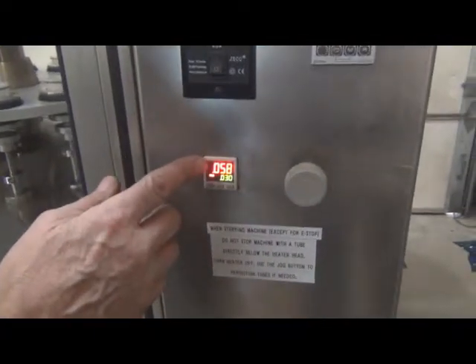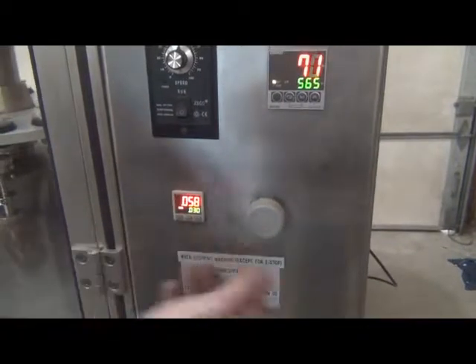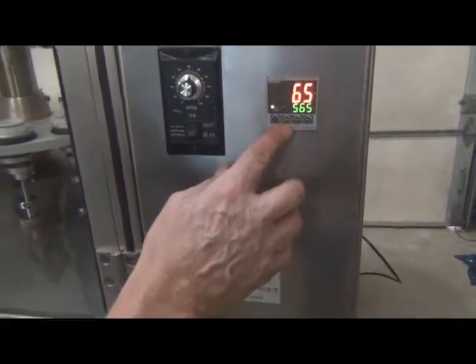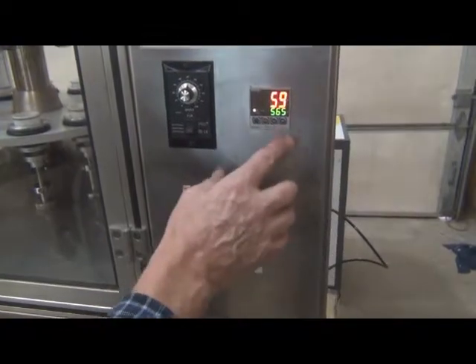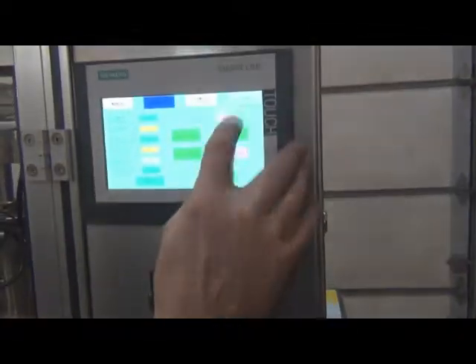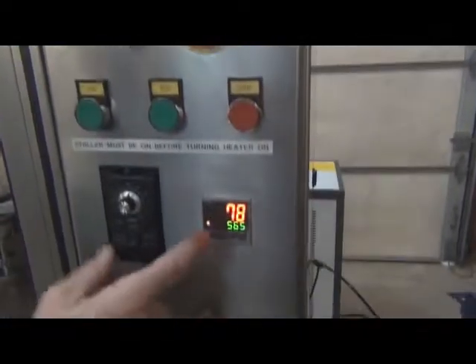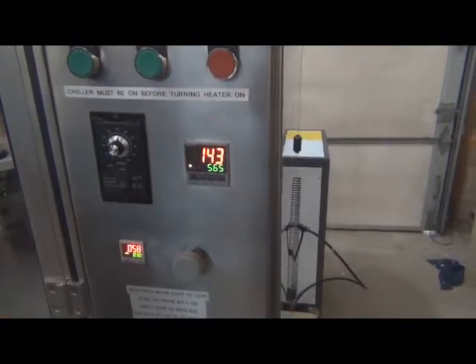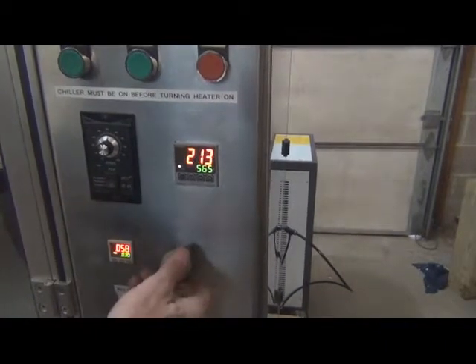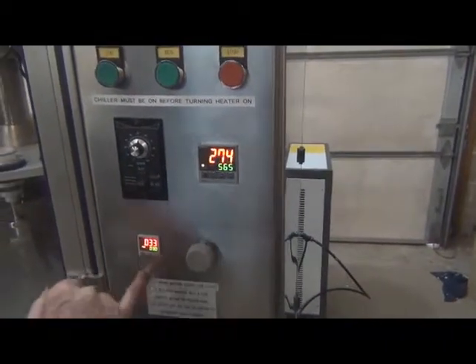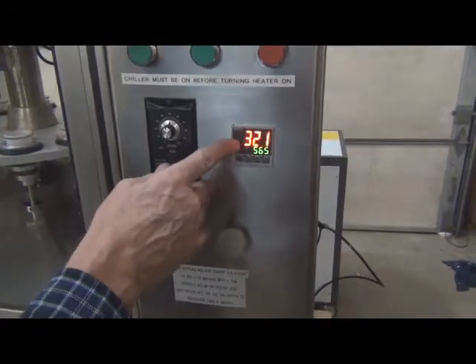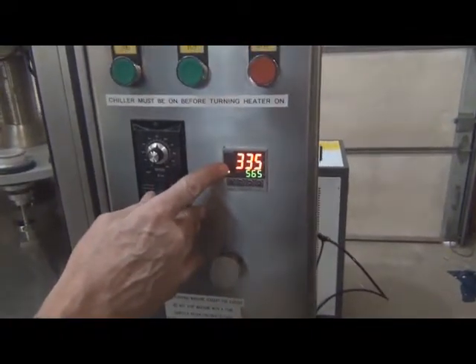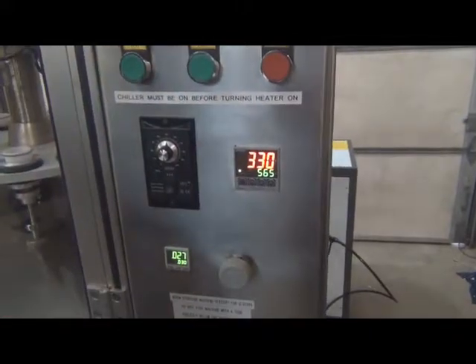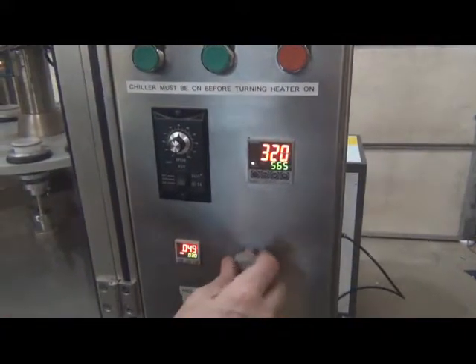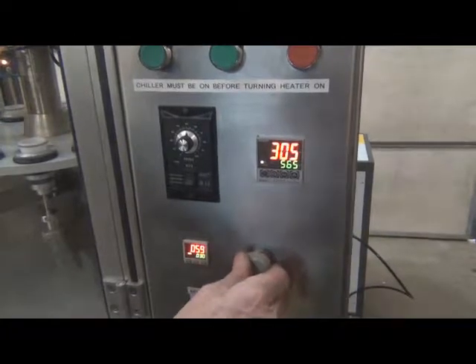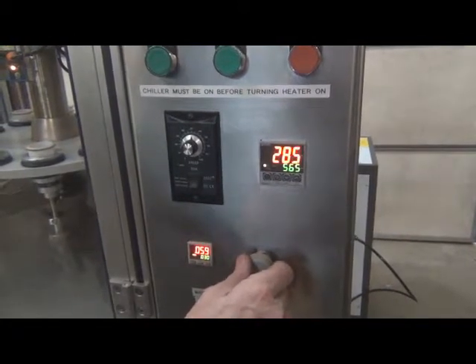This is here. That's your display. Now below that, if you turn that below, it will turn the heater off. Actually, the heater. I'll show you. I'll turn the temperature on. Now it's calling for heat. You'll see it rises pretty quickly. But if you lose air to the blower, if this goes below 30, that will de-energize. You'll see it's down. It peaked. Now it's going to come back down. So it needs to have air blowing past the nozzle. It'll burn everything up without it.